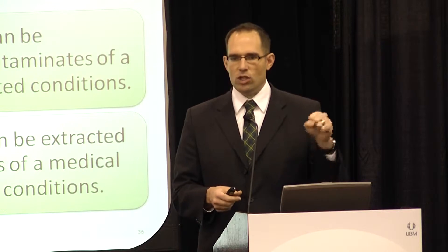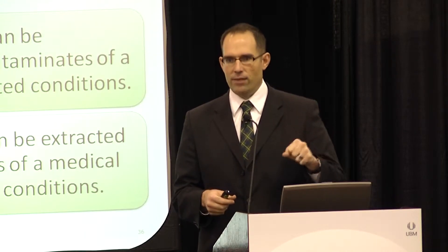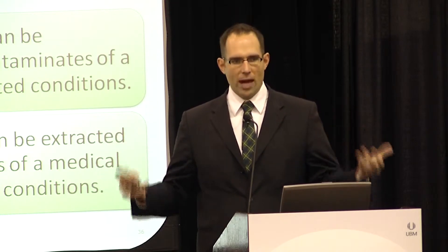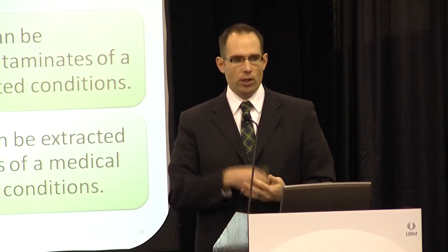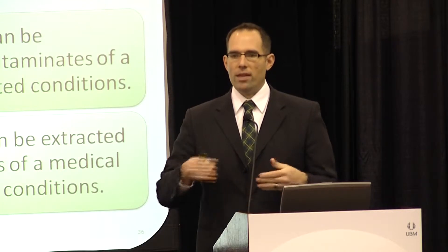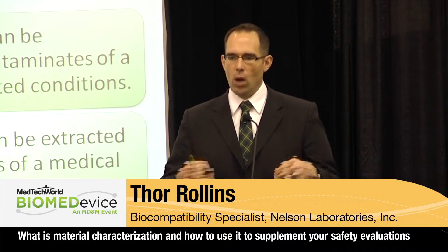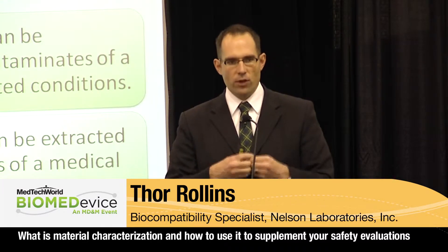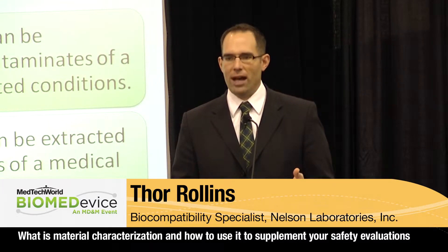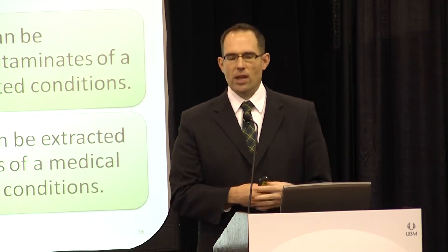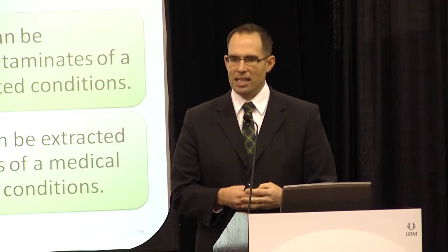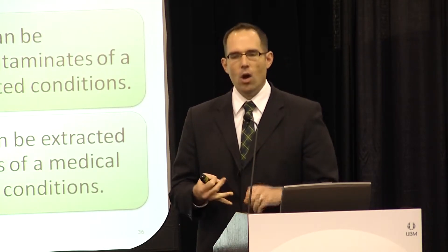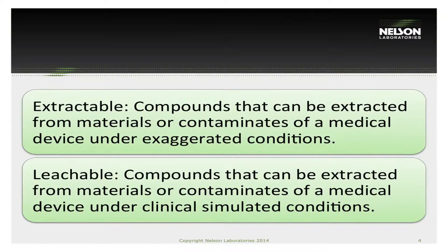Leachables are always a subset of extractables — you're always going to get more off in the extractable case than with leachables. So one thing we can do is run the extractables test to see what comes off, and if you're safe using the extractable profiles, that should cover your leachables. You have to decide: do you want worst-case extractables, or do you want to look at the clinical simulation?